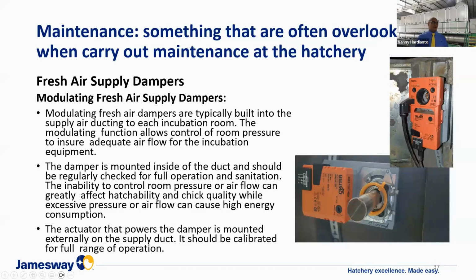Okay, next is the modulating damper. The modulating damper is typically built into the supply air ducting to each incubation room. The modulating function allows control of room pressure to ensure adequate airflow for the incubation equipment. The damper is mounted inside the duct and should be regularly checked for full operation and sanitation.